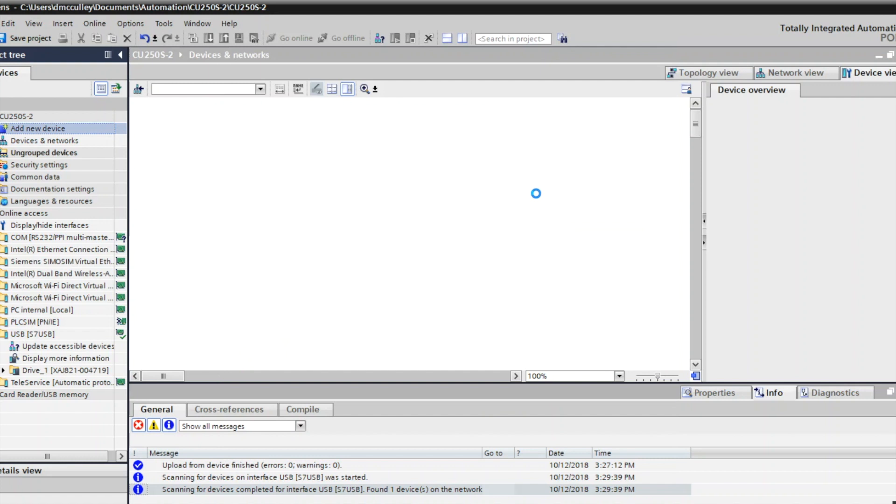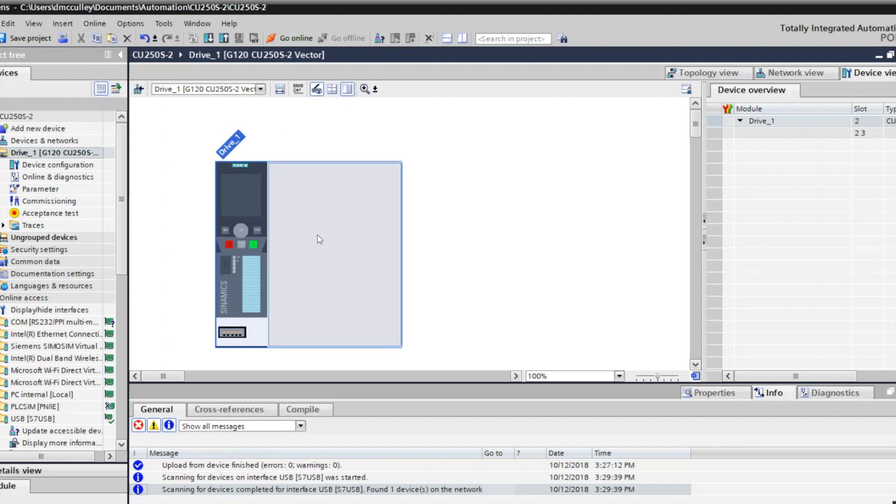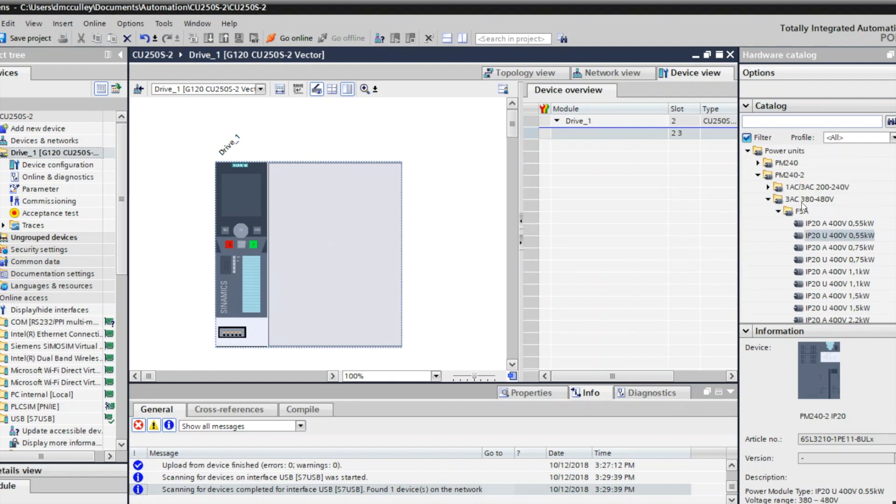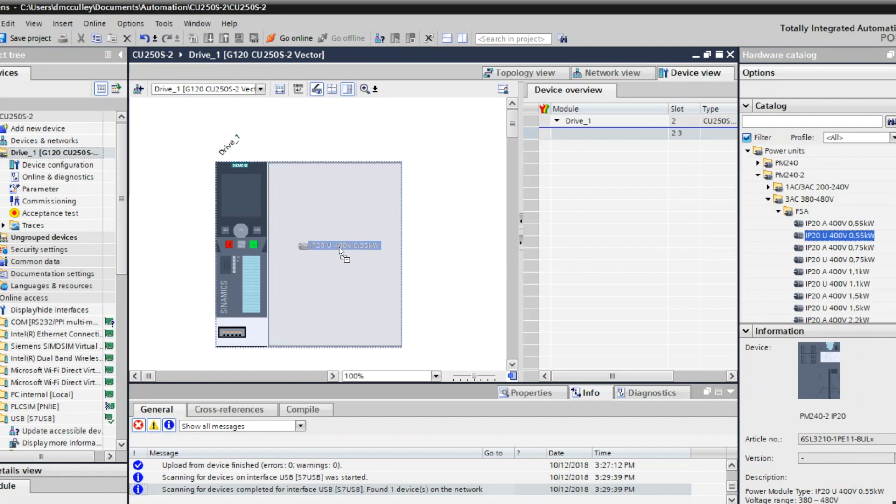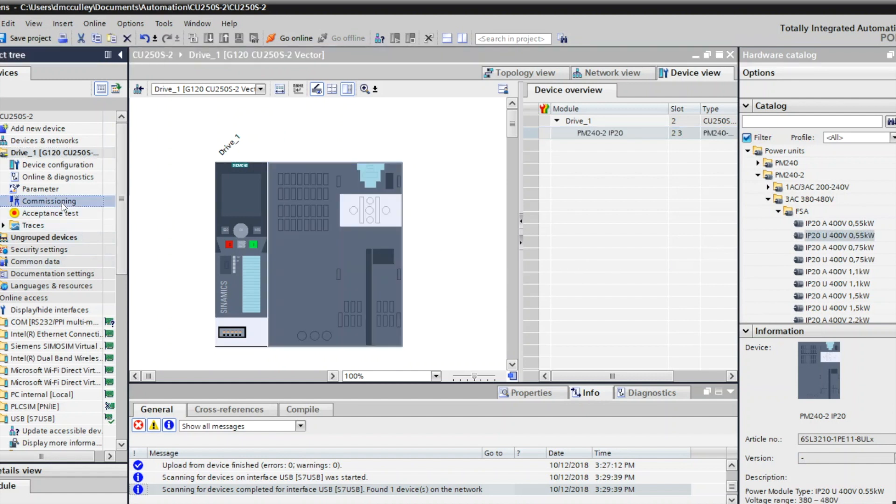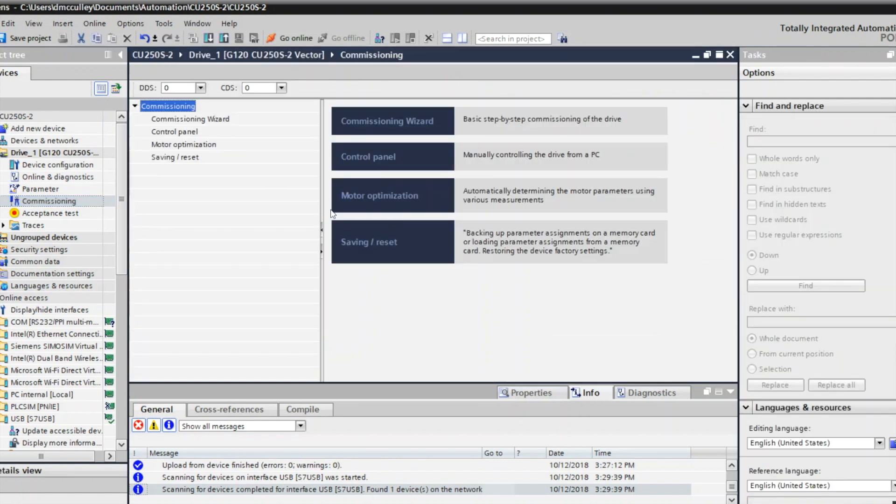I'll click OK. That'll get into my network view, my device view, and then I need to add a power module with a hardware catalog. I've got a 480 volt frame size A, 0.55 kilowatt drive without the filter. I know this is correct, so I'll drag it over. That's my power module, and now I can commission the drive.